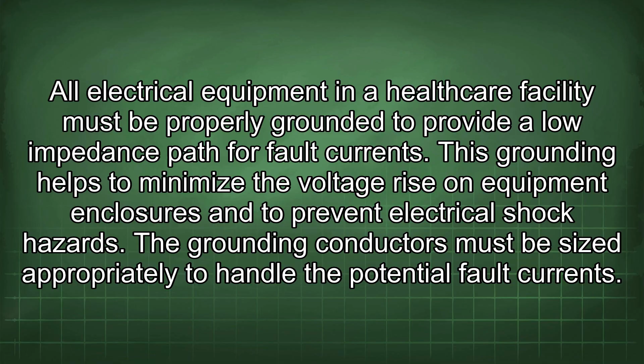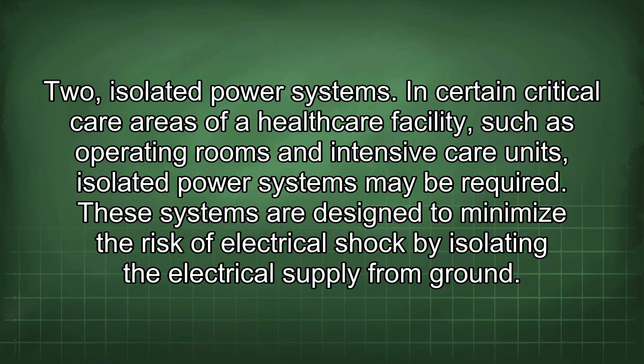Second, isolated power systems. In certain critical care areas of a healthcare facility, such as operating rooms and intensive care units, isolated power systems may be required. These systems are designed to minimize the risk of electrical shock by isolating the electrical supply from ground. Isolated power systems use a special transformer that does not have a direct connection to ground.